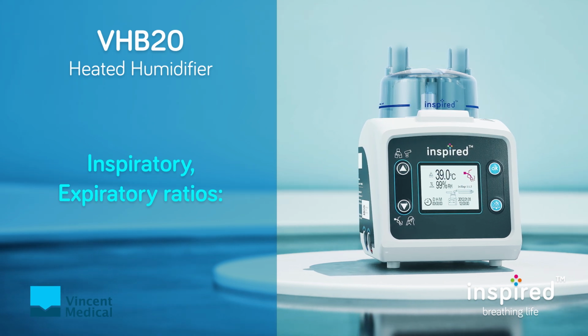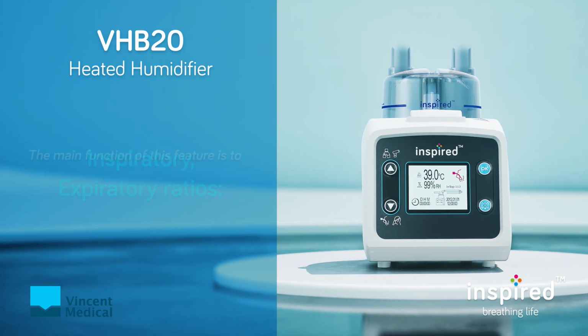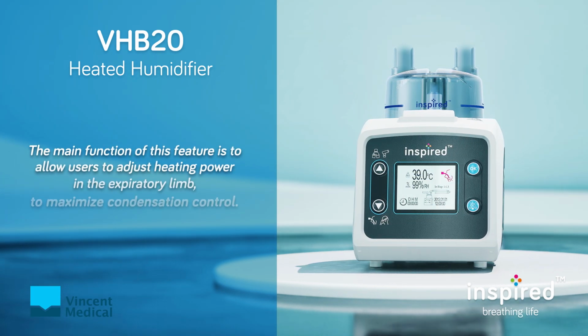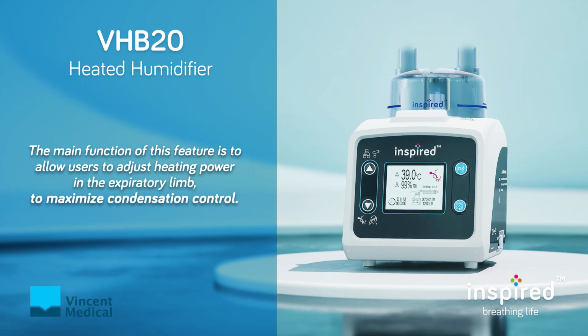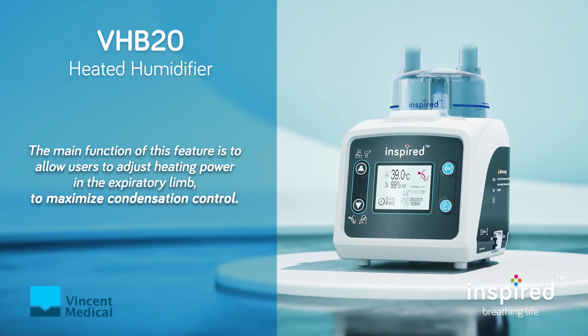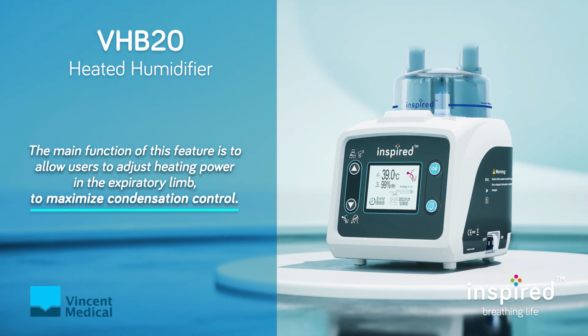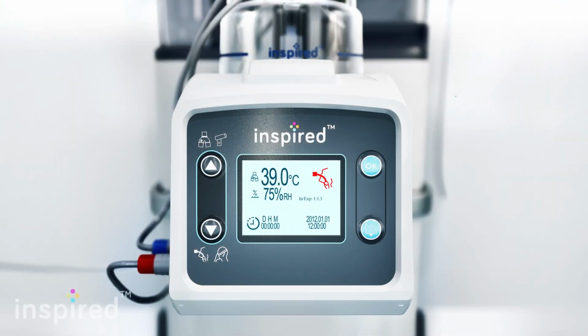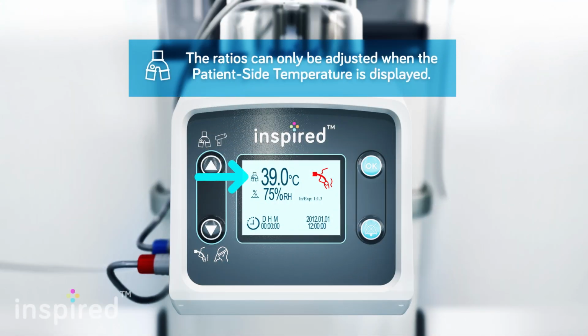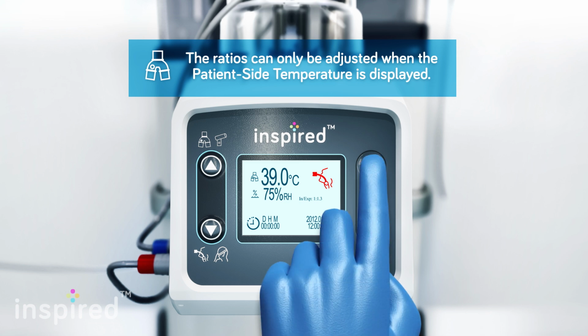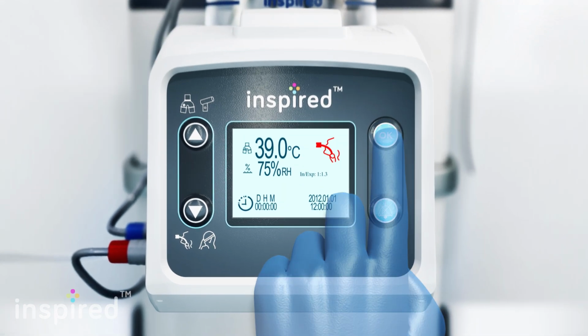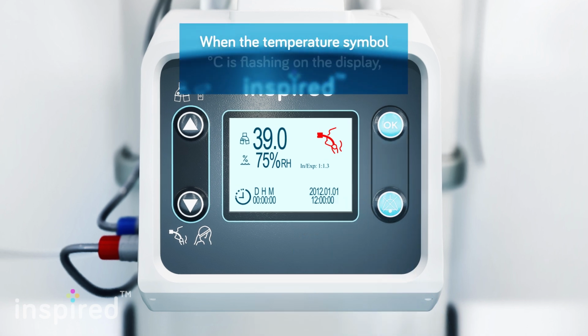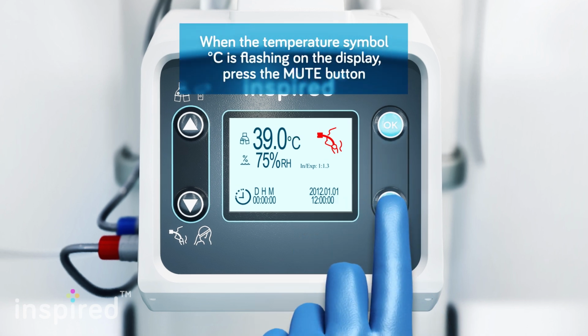Inspiratory-expiratory ratios. The main function of this feature is to allow users to adjust heating power in the expiratory limb to maximize condensation control. The ratios can only be adjusted when the patient side temperature is displayed. Press and hold the OK button for 3 seconds. When the temperature symbol degrees Celsius is flashing on the display, press the mute button.